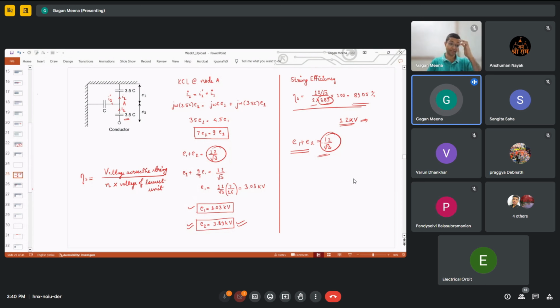And that provides us very important information, and that is why we are calculating this efficiency also. If you take E1, E1 is 3.03 kV, E2 is 3.89 kV. We have to design all the insulators with the highest voltage. We cannot have insulators of different voltages, because there is a standardization for everything. If we make insulators for different voltages, then for each transmission line it will be different, and we'll have to keep spare parts for each transmission line. That is not an economical proposal.